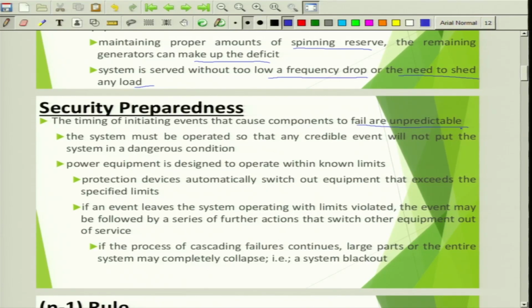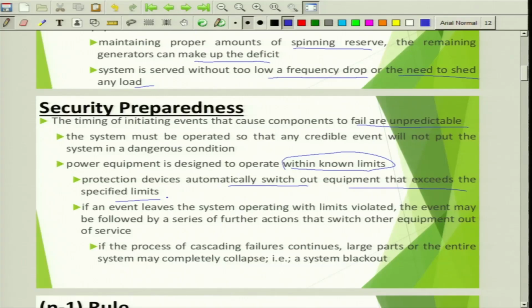Power equipment is designed to operate within known limits. There are limits for each and every component. Protection devices automatically switch out equipment that exceeds the specified limits. There are relays and circuit breakers placed. If there is a specific violation of the limits, thermal limits or voltage limits or whatever, then it is supposed to take out the specific equipment. If an event leaves the system operating with limits violated, the event may be followed by a series of further actions that switch other equipment out of service.